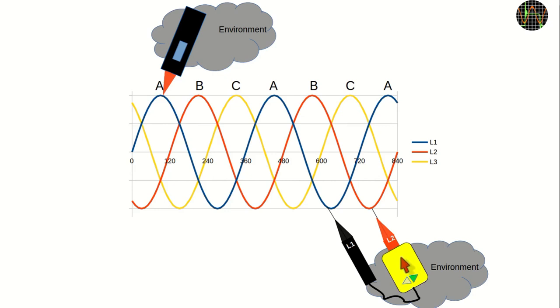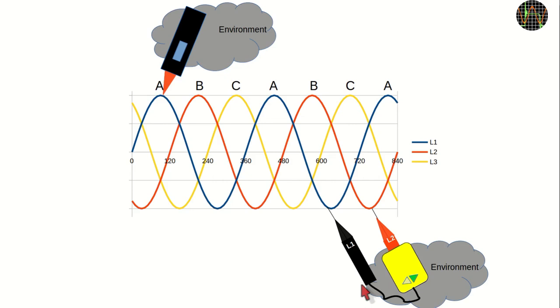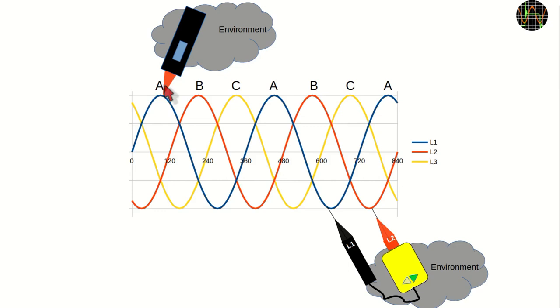I think the problem for both the Fluke and the ST120 is that there is not any phase reference for the meters to pick up in my crude test setup. The Fluke manual explains that the T110 examines the two phase signals but picks a reference capacitively from you holding it in the hand. Obviously, that reference isn't the tiny stuff coming from my test setup, but rather the much larger general mains hum from all my equipment in the room. If the Fluke gets confused in its phase sequence even when connected to two phases simultaneously, it is no wonder that the ST120 with just one connection can't work it out either. And connecting the black lead of the ST120 to the transformer obviously isn't the same as a phase reference that stays the same when measuring a different phase. So without access to a real three-phase system, all I can say about the phase sequence mode of the ST120 is I demonstrated how it would look like and I think it probably works fine.